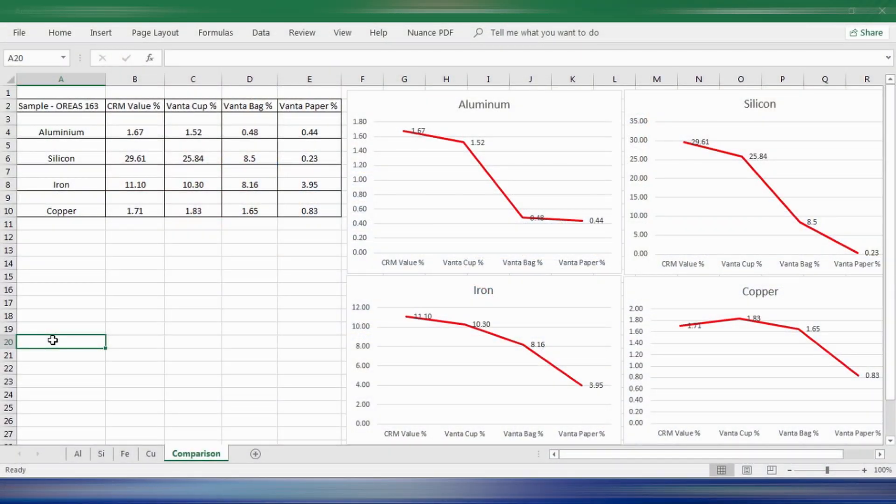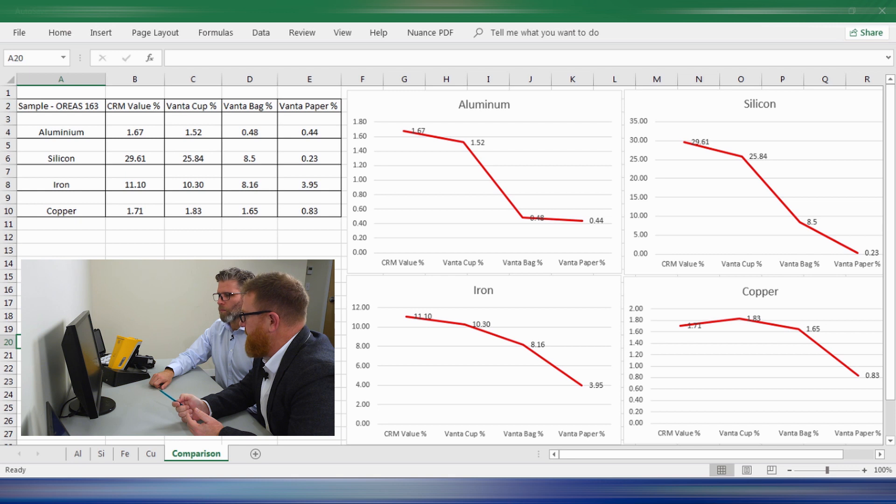So Todd, tell me something about this data. Okay. When we plot up all the readings we took, the first thing I notice is we're reading quite close through cups to the true CRM value. But maybe we could have tested for a little bit longer, because we only did quite short tests. Yeah, we only did a 20 second test time on each medium, Todd.